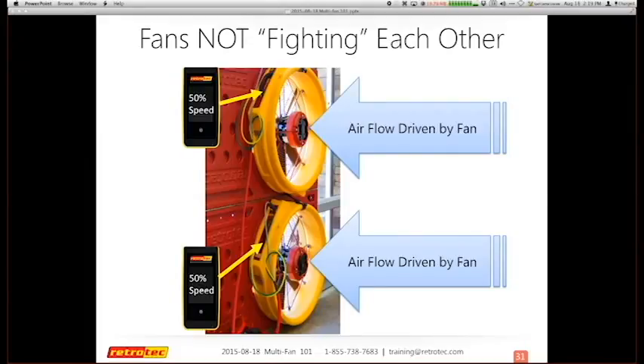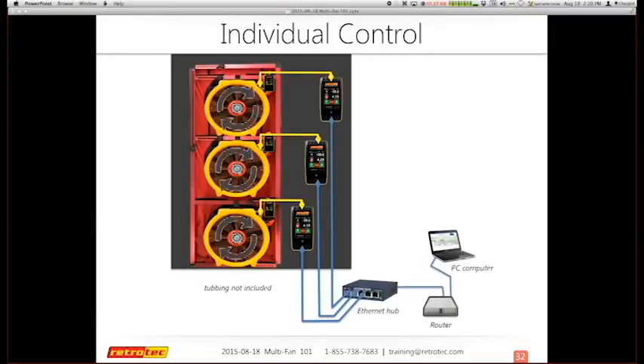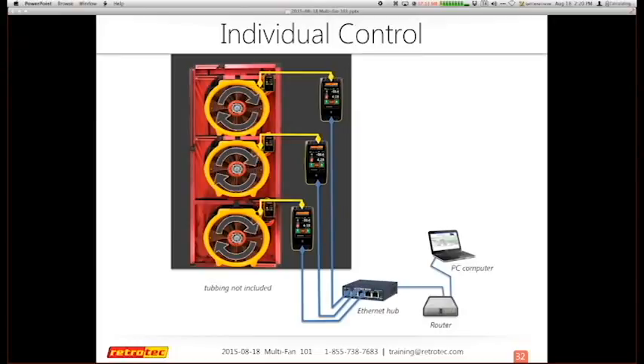A common flaw is when people connect their gauges as though they normally might for a single fan. What happens is the fans begin rotating the same way, but then some slow down and begin to go in reverse. If they're not in your direct line of sight this can be a challenge. Those doing large buildings will actually walk around their fan banks with a thermal imaging camera to see which fans are not at the same temperature — indicating a fan that has stopped or is moving in the opposite direction.